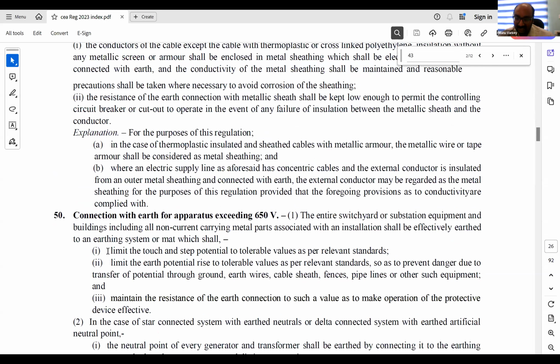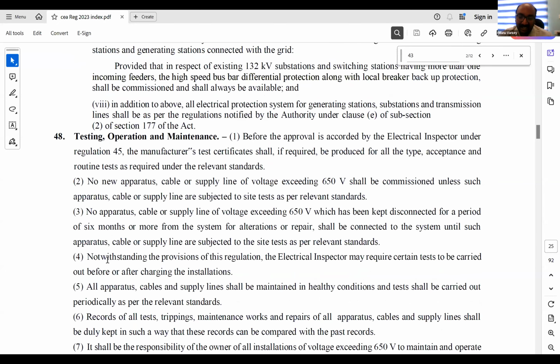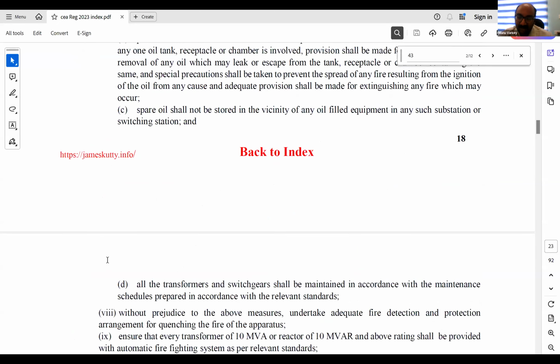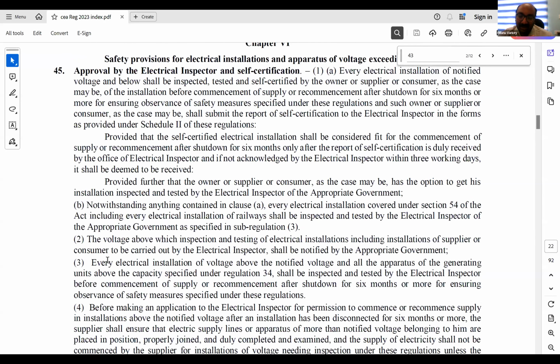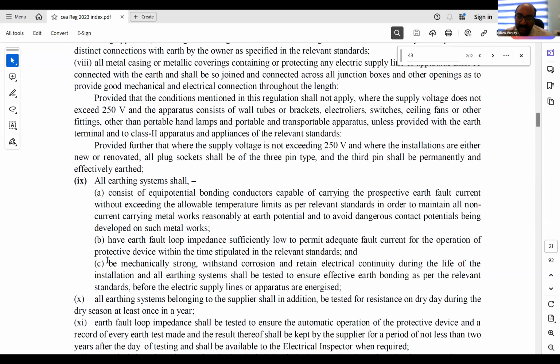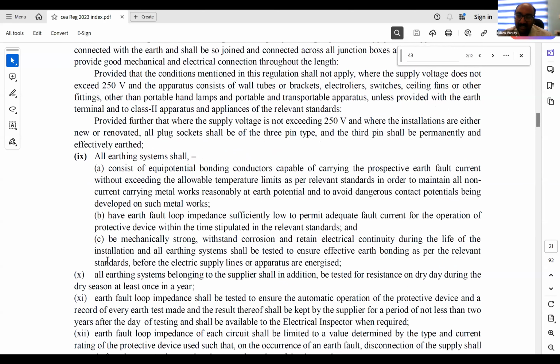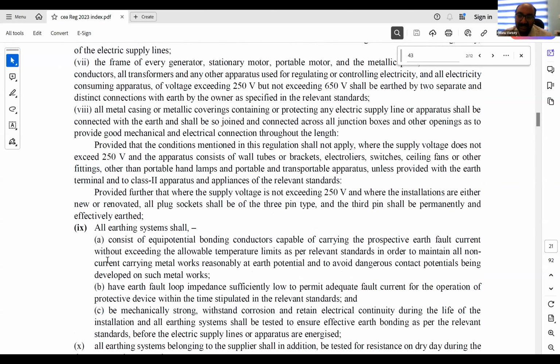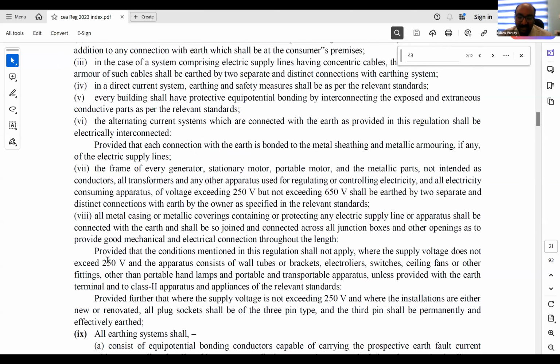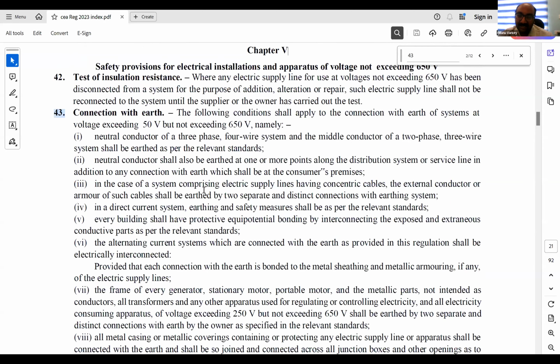of the earthing system. However, if we come to the LT side, this is dealt with in Regulation 43. Here, to ensure a reliable earthing system, more than the earthing resistance, it should be the reliance on automatic disconnection of supply. For automatic disconnection of supply, we should have a loop impedance that is sufficiently low that will cause operation of the protective device in the event of a fault.